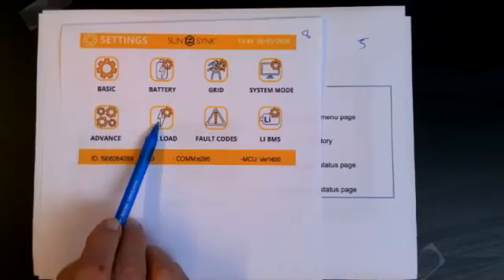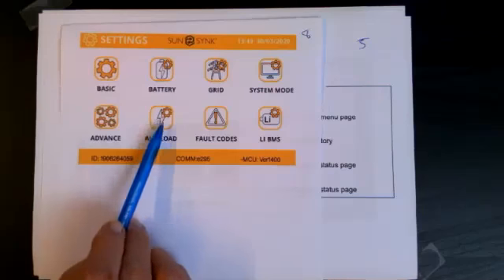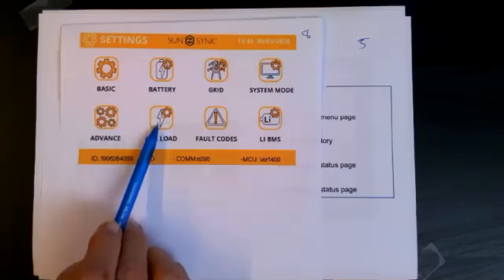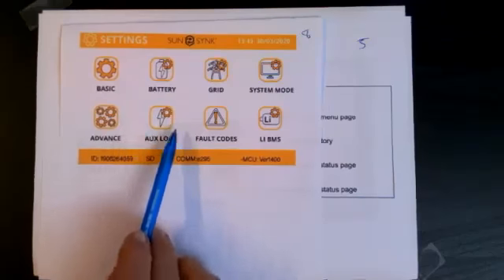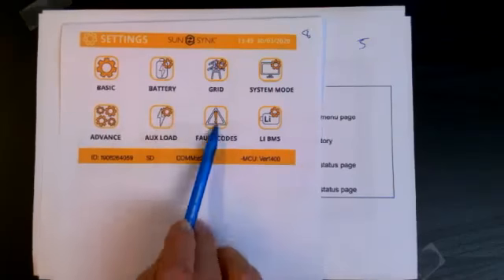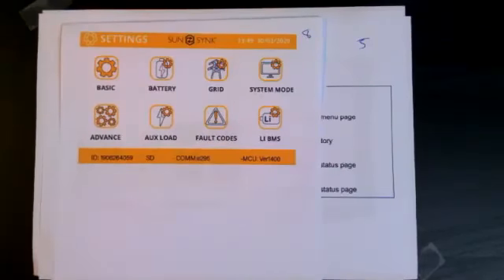Auxiliary load, this is where we're using the auxiliary or the gen port. It can be working a generator. It can be working a microinverter. And again, this is more advanced, and I'll go through this another time. Fault codes. I just mentioned one thing about fault codes. Fault codes are a diagnostic tool. It doesn't mean the inverter is faulty.